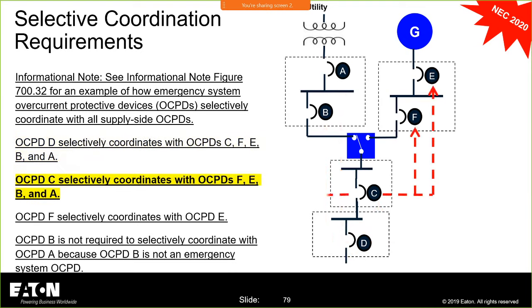Now we're going to look at C. C has to selectively coordinate with all line side overcurrent protective devices. It is on the emergency side. So the onus to selectively coordinate with A and B is on C. And I may, again, have to make changes in A and B to meet this requirement, but the onus is on C to selectively coordinate with B and A. Okay, and I will probably have to make changes to B and A to accommodate this requirement. But if you could get it done with making a change to C, get it done that way. But otherwise, you're going to have to address it.